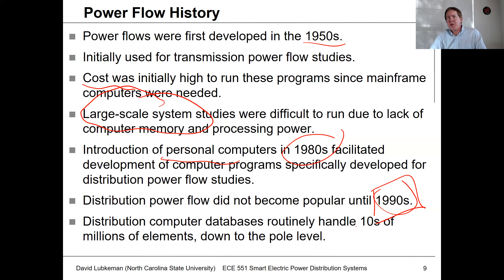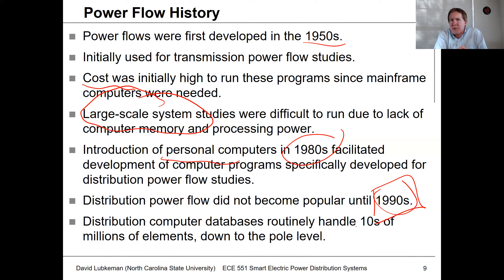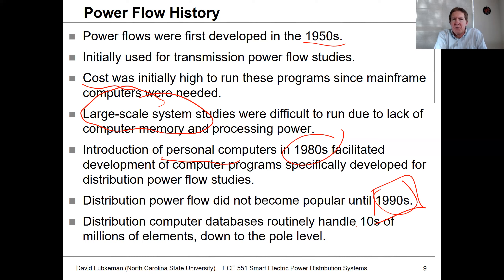The other thing about distribution is that distribution circuits have a lot more discrete elements than transmission. Nowadays we model almost down to the pole level, certainly down to the distribution transformer level. In a distribution database for a utility, they would have tens of millions of elements because they're basically modeling all the way down to where individual poles are located. A lot of times this is coming right out of a geographic information system and going right into computer analysis. Even though the circuits don't seem that complex from a modeling standpoint, they're actually a lot more complex than transmission.